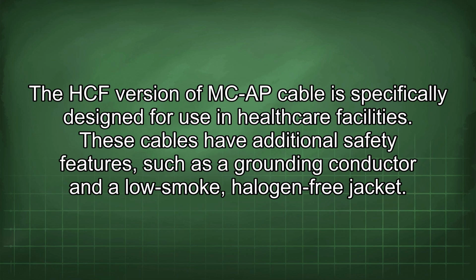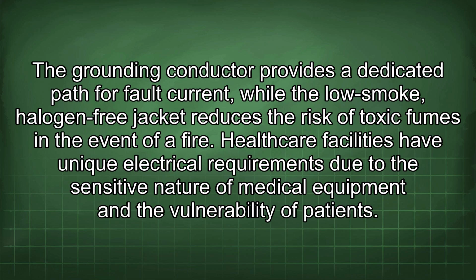The HCF version of MCAP cable is specifically designed for use in healthcare facilities. These cables have additional safety features, such as a grounding conductor and a low-smoke, halogen-free jacket. The grounding conductor provides a dedicated path for fault current, while the low-smoke, halogen-free jacket reduces the risk of toxic fumes in the event of a fire.